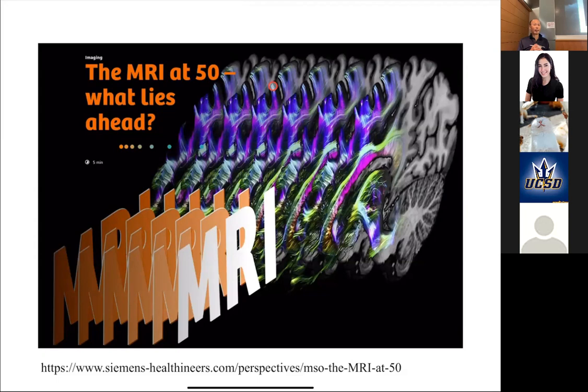and people are still trying to figure out the best method for that. But if you can track the motion, sometimes they'll use optical detectors, they'll put little beads and then you can have a camera detect the motion. And then if you know the motion, you can actually change the gradients to follow, right? And keep the volume the same.